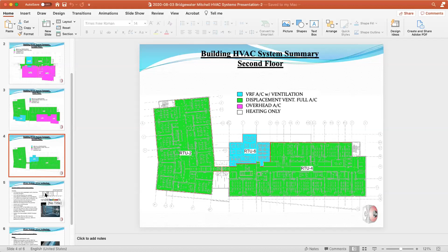So that was another point that is in the design. Mr. Pacheco really wanted to see that in the design, the supplemental hot water radiation, so that in the event of a VRF failure, these areas would still be heated by the hot water system. That's a summary of what we went through in control diagrams on a more technical level at the working group meeting. And then the other subject that we covered was some potential supplemental technologies that are gaining interest in the HVAC industry, in addition to increasing filtration effectiveness, adding supplemental technology.